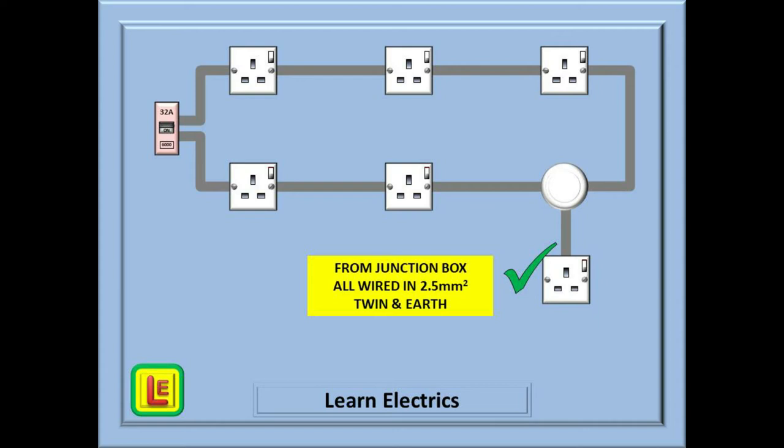We could have a junction box on the ring that supplies a socket. As long as the cable that connects the socket to the junction box is 2.5mm then all is okay. In fact, we could do this to every socket or junction box that is actually part of the ring. A single accessory can be attached to each accessory on the ring if the rules are followed. A double socket is classed as a single accessory as it is still only one piece of plastic. But two single sockets next to each other are not allowed. Unfortunately, those are the rules.